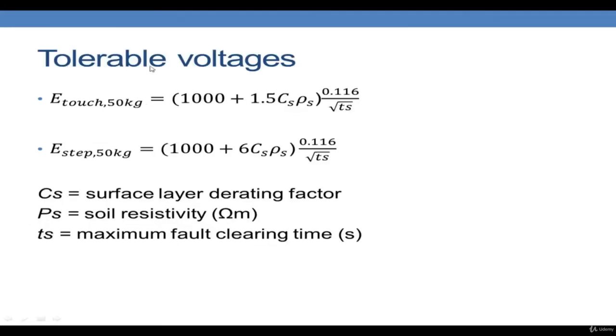So next we will look at the tolerable voltages. The touch potential for a person having 50 kg weight is given by this equation over here, where CS is the surface layer derating factor. This is the correction factor we use because in substations, in order to minimize the step potential, we usually place granite rocks or crushed rocks, and in order to correct the actual soil resistivity, we use this term over here, the correction factor considering the effect of the crushed rock. And this is the step potential for a 50 kg person. Here rho S is the soil resistivity given in ohm meters, and tS is the maximum fault clearing time in seconds.